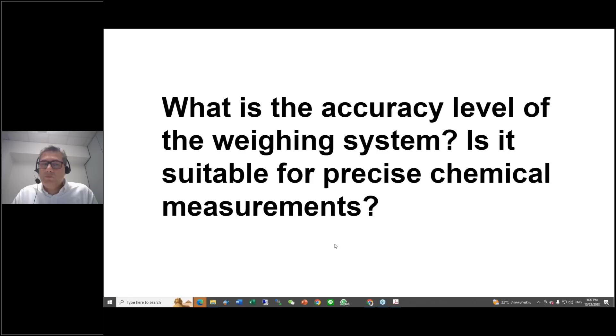Is the weighing system equipped with load cells or other weighing sensing devices? How are they calibrated and maintained for accuracy? Along the machine, in front of each individual feeder, we have a load cell, in the triangle frame that we saw in one of the slides. That frame also lifts up the bucket. Below the frame, there is a high precision load cell with 40,000 divisions that allows a very precise and highly repeatable process.